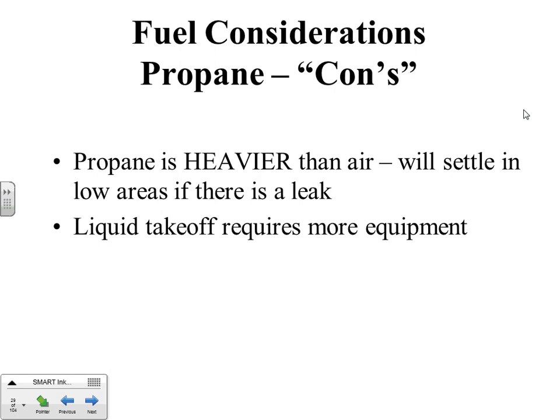And I always tell engineers, make sure that all of the tanks and everything are outside and never bring liquid into a building. So you do the vaporizing, if you're going with a liquid takeoff, you do the vaporizing of that system outdoors. And then everything, hopefully not in a low area. Keep it up on a hill, higher area for locating the tank and stuff. So real life issues.